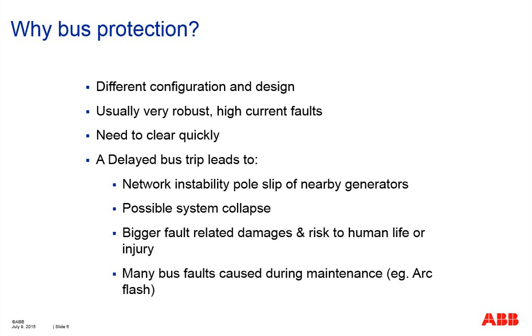On medium voltage or low voltage switchgear, busbar protection now has also become a necessity because of arc flash related security requirements. If the switchgear is not equipped with arc flash protection, for example, a dedicated light sensor or laser sensor sensing arc flash, busbar protection is typically required in order to reduce the damaging sound, light and heat waves projected from any arc flash scenario condition.